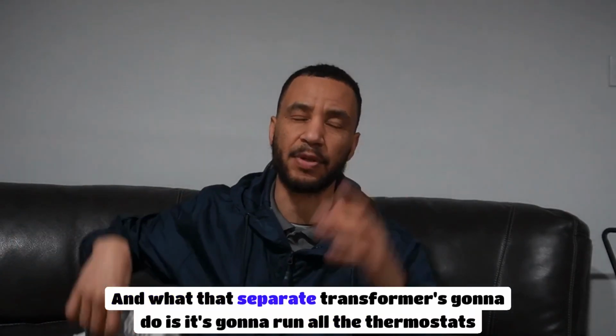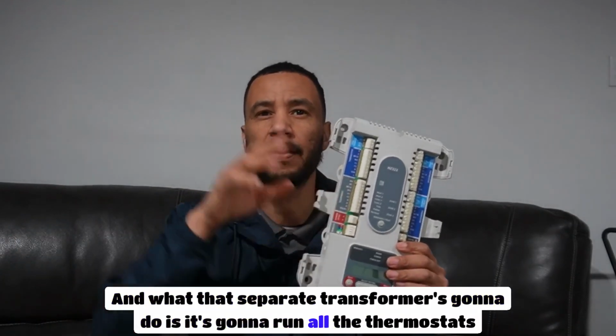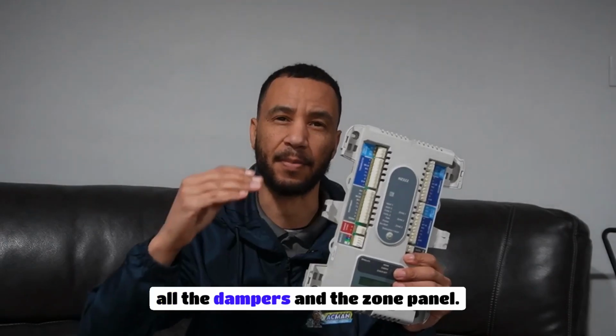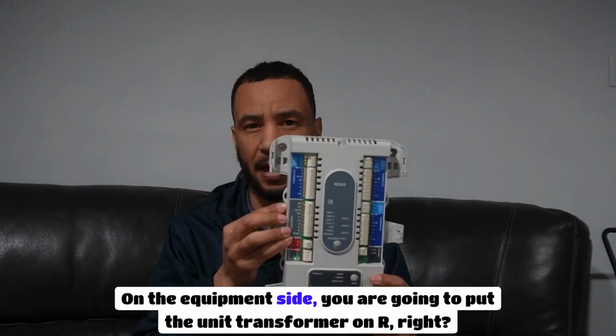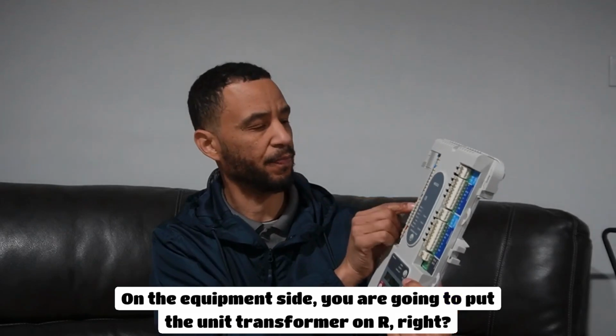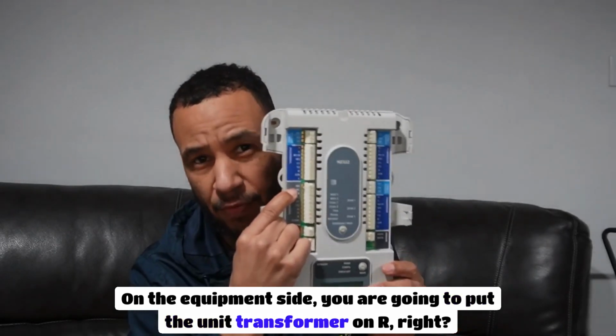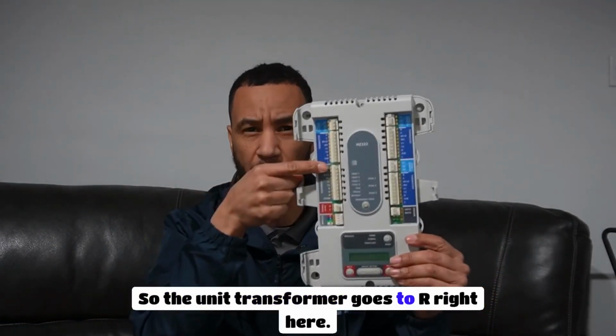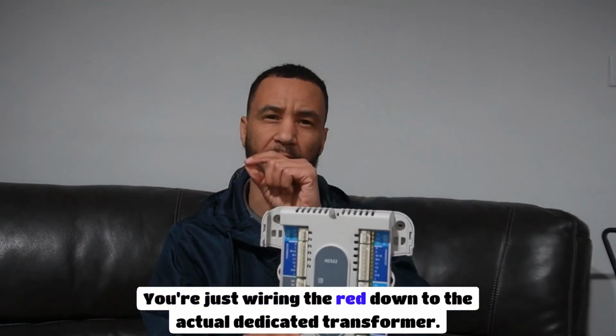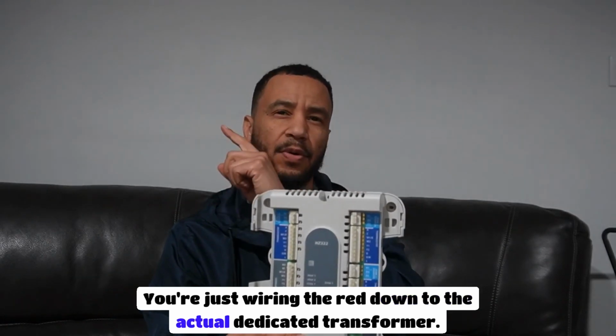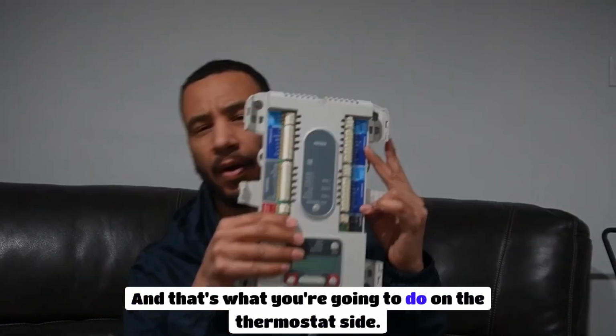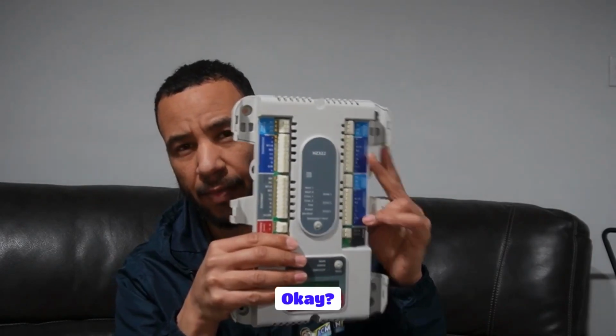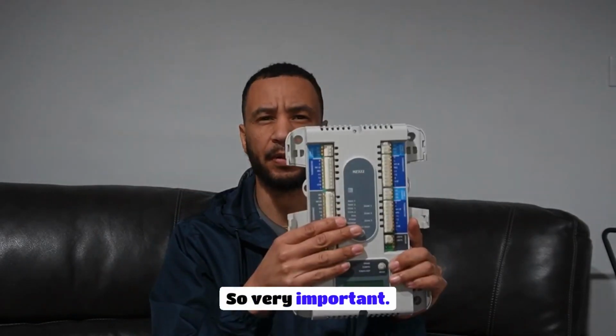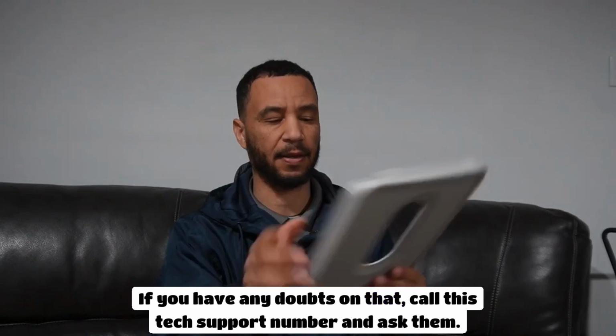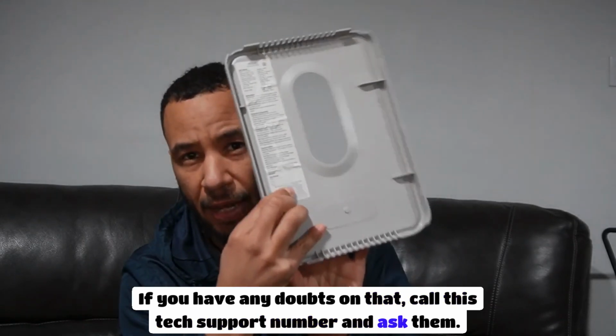And what that separate transformer is going to do is run all the thermostats, all the dampers, and the zone panel. On the equipment side, you are going to put the unit transformer on R, right? Okay, so the unit transformer goes to R right here. You're just wiring the red down to the actual dedicated transformer, and that's what you're going to do on the thermostat side, okay? So very important. Remember that. If you have any doubts on that, call this tech support number and ask them, all right?